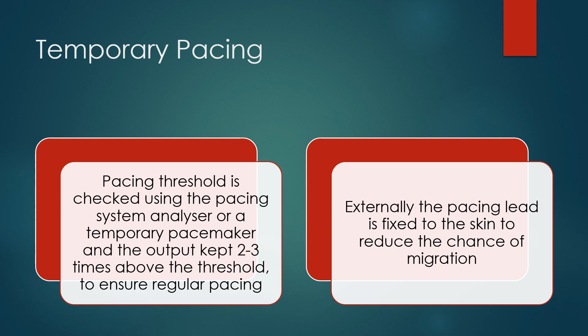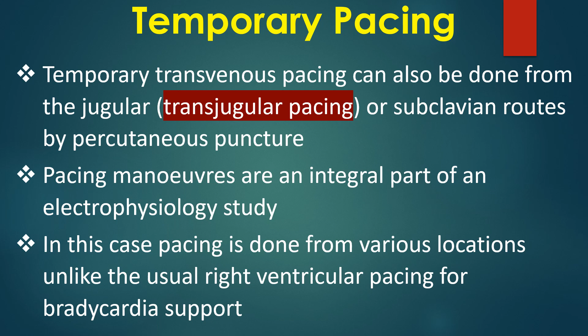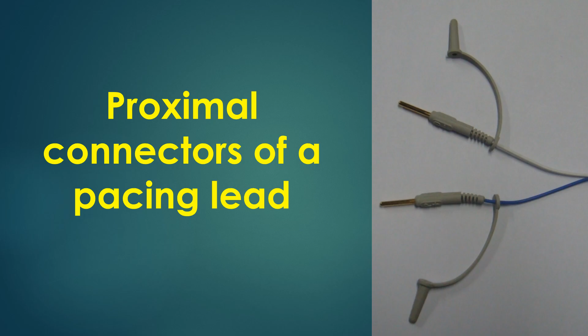Pacing maneuvers are an integral part of an electrophysiology study. In this case, pacing is done from various locations, unlike the usual right ventricular pacing for bradycardia support. Proximal connectors of a pacing lead are shown in this image. Tip of the bipolar temporary pacing electrode has a distal tip electrode and a proximal ring electrode. It is customary to give negative polarity to the tip and positive polarity to the ring electrode, as cathodal pacing has a lower threshold.